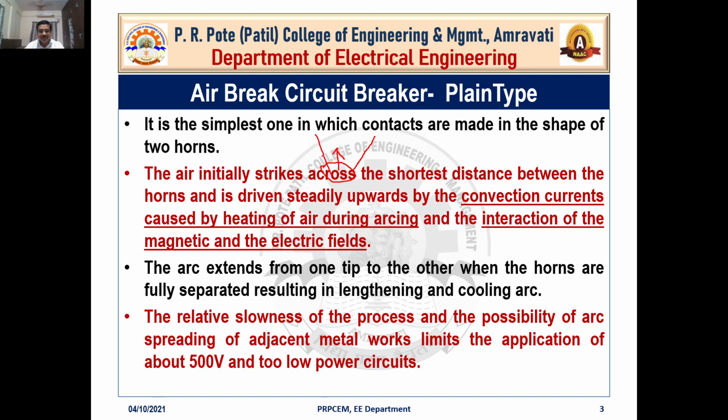This is also possible with the help of convection current. With the help of the convection principle, because the air is heated up when we are blowing it, since the arc is present there, and there is also an interaction between the magnetic and the electric field, this particular arc will be traveling from the narrow opening to the wide opening, because we have this particular arrangement where we are directing the path of the arc.